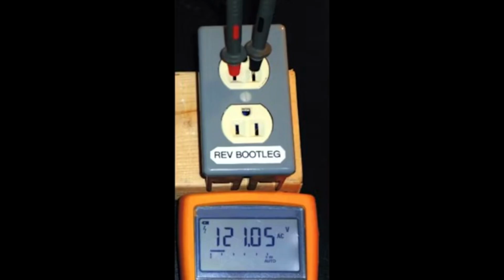You really do want to try to put the black lead in first. If you start with the hot side first, now that black probe wire that's in your hand flying around and touching your leg and everything is an electrocution hazard. Just because if you complete the ground, that black wire is now hot and it'll bite you pretty good.